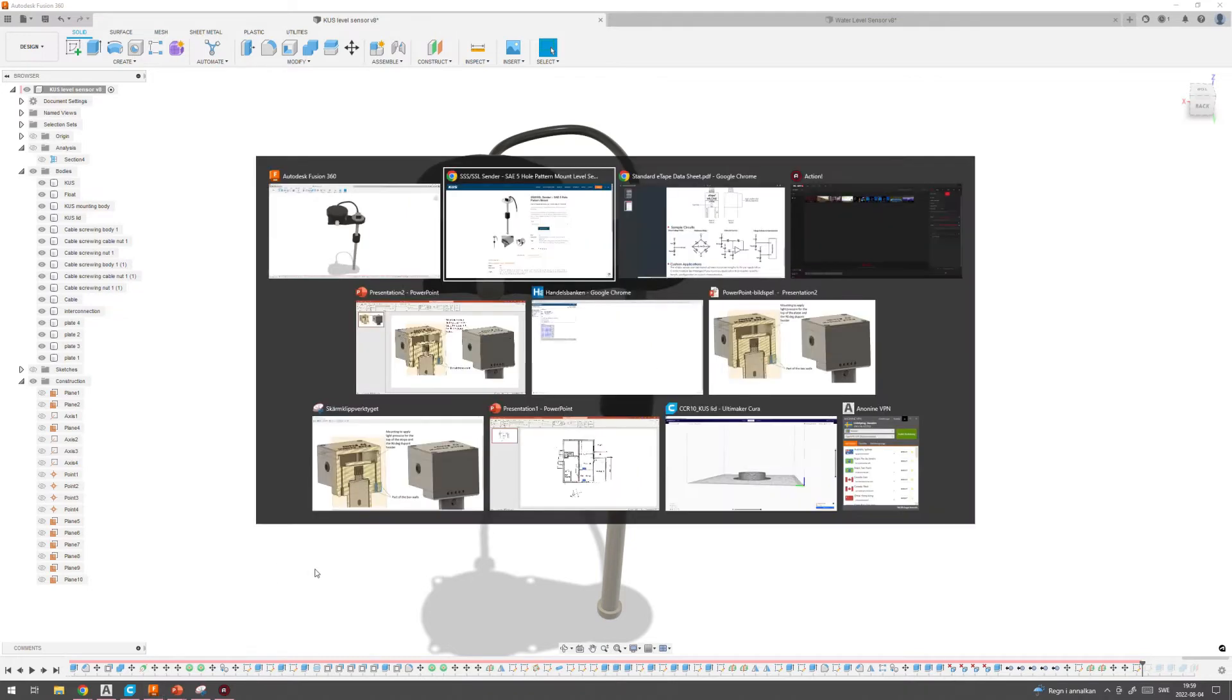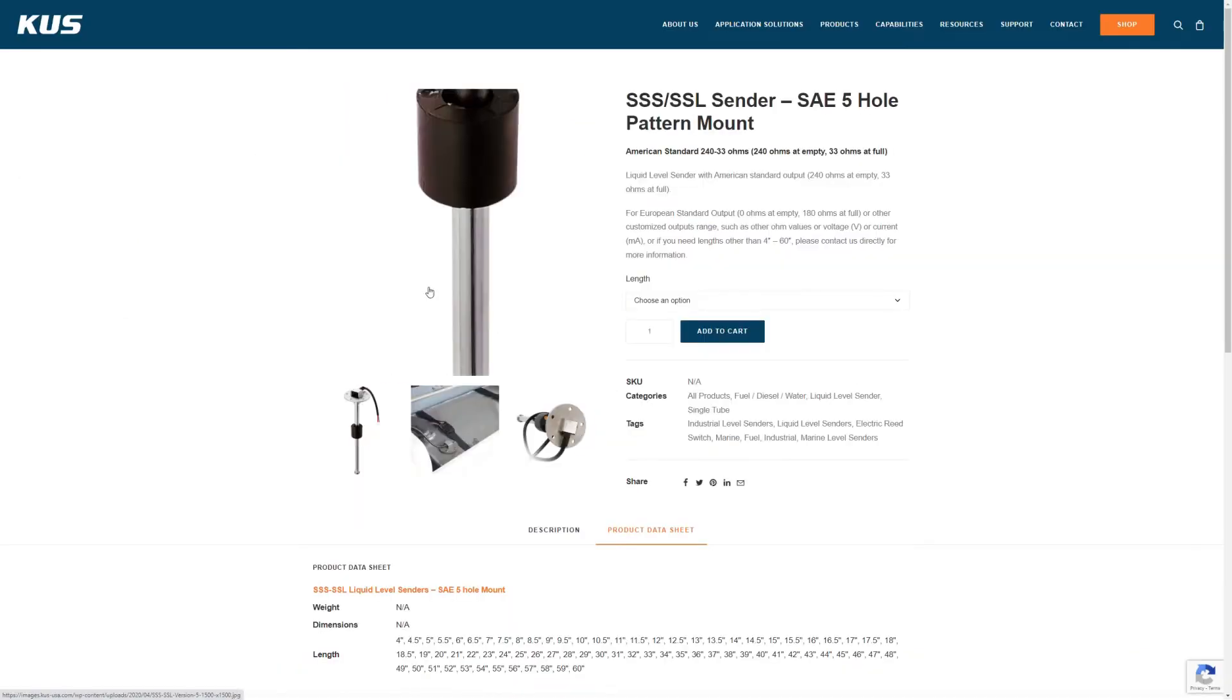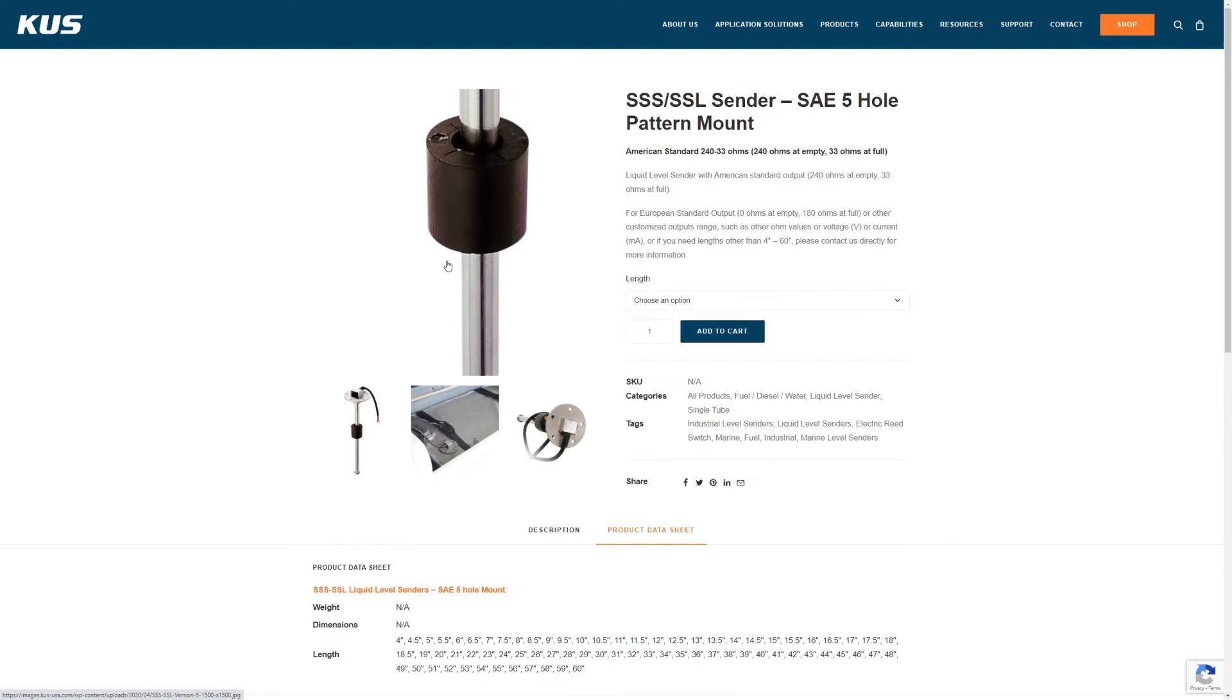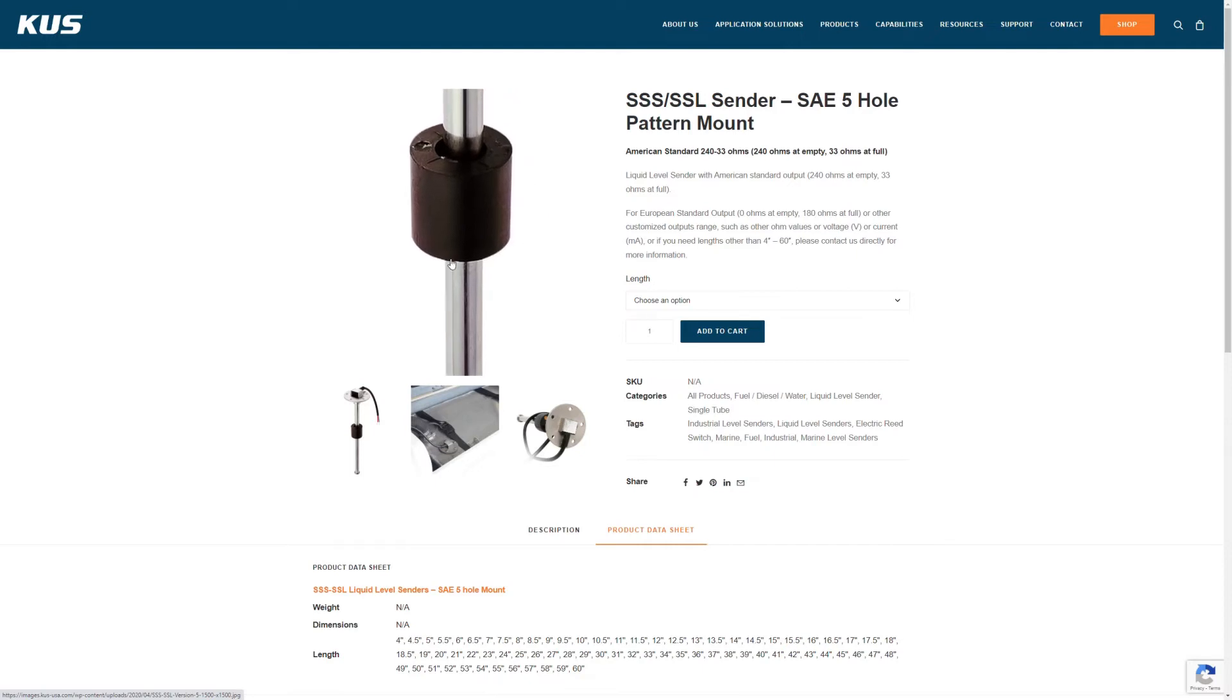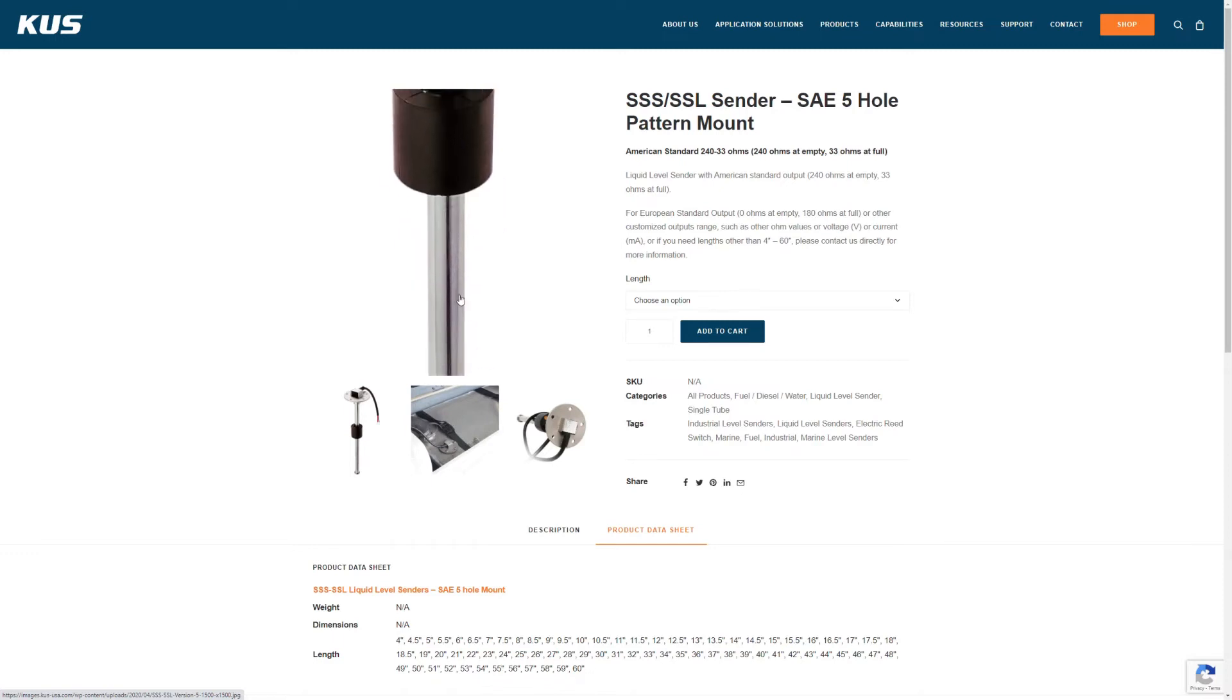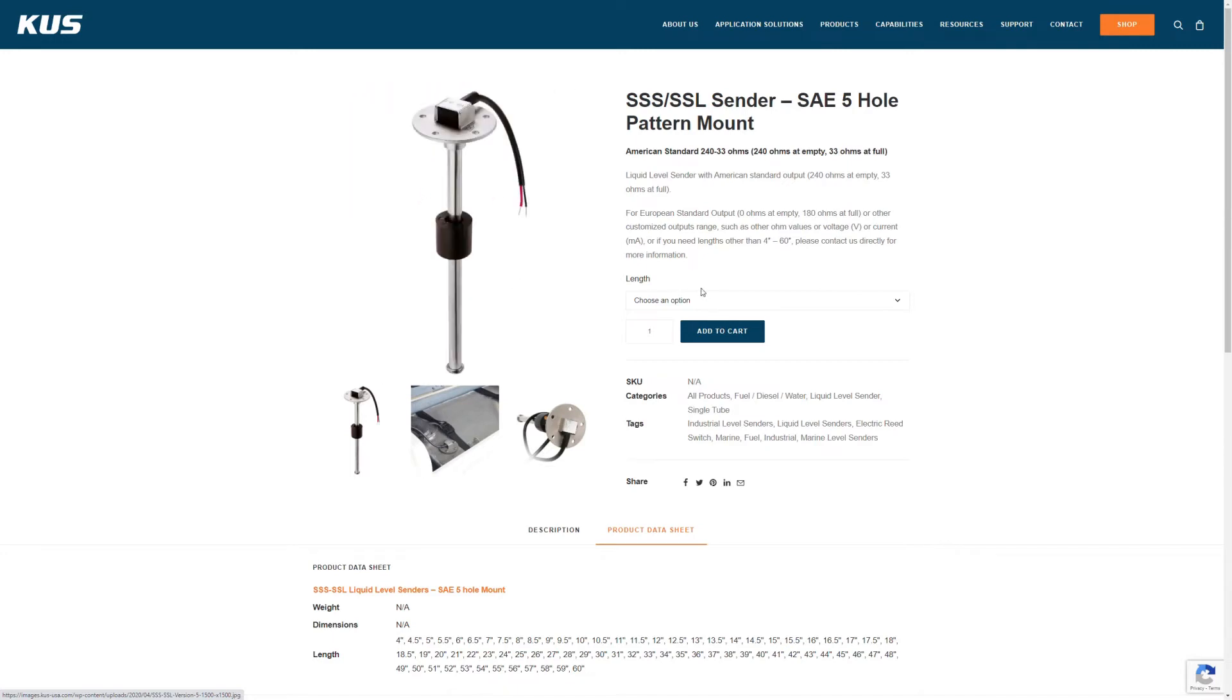These level switches have a pretty bad accuracy from a datasheet point of view, so it says accuracy of 21 millimeters. But in the way that these work with the reed switches that you have in the tube here, they have sort of a built-in hysteresis, so once it has been activated and going down, it will have some delay.